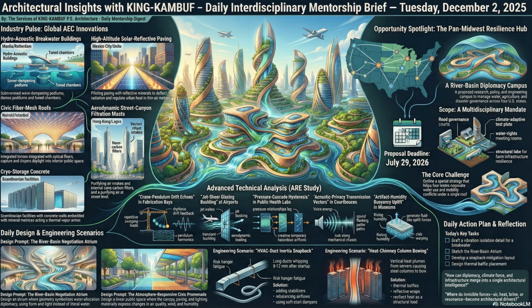That's a great way to think about it. And during that lag time, the intended containment cascade can temporarily fail or even reverse, creating an unintended and potentially hazardous flow direction. Transient airflow, the movement during the adjustment, can be far more dangerous than a steady-state failure because it's so unpredictable. So what's the takeaway for commissioning these buildings? The commissioning process has to include rigorous testing of these hysteresis cycles. You have to ensure that the system recovers its intended pressure relationship quickly and predictably to minimize that risk window for biocontainment breaches. Okay, let's pivot from invisible flows to dynamic forces, loads caused by movement, asymmetry, or repetitive impact.